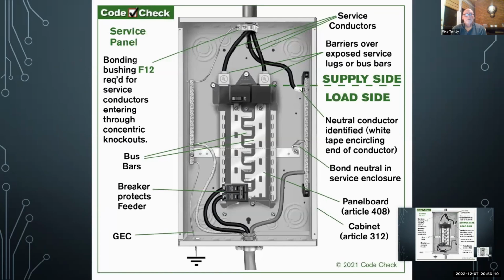Okay, here's another one of the code check slides. It's a good illustration. This is a service equipment panel. I don't know if you guys can see my cursor if I move it around? Yes. Okay. All right. This is the service neutral coming in to this bar. This bar is elevated off of the can, so some people call it floating. I guess that's a good term. This is the bonding jumper that ties this, and this screw is tapped into the back of the can like we talked about before. This is a tie bar going across to this other terminal.